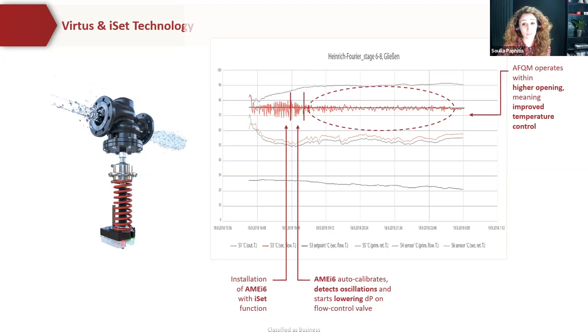As you can see from the graph here, and this is a real life case study that we've been involved in, you can see the benefits of installing this technology. On the left-hand side there are big flow and temperature oscillations, measured on the secondary network, especially during the low demand periods. In the middle portion, you can see where ISET has started to kick in, and it's starting to lower the differential pressure control and oscillations. It also shows on the right-hand part of the graph where ISET is fully functioning. It's learnt the demand flows from the heat exchanger and the system itself, and it's starting to provide much better comfort conditions for the end users. So this is the part that's being delivered into your tertiary side of the system.